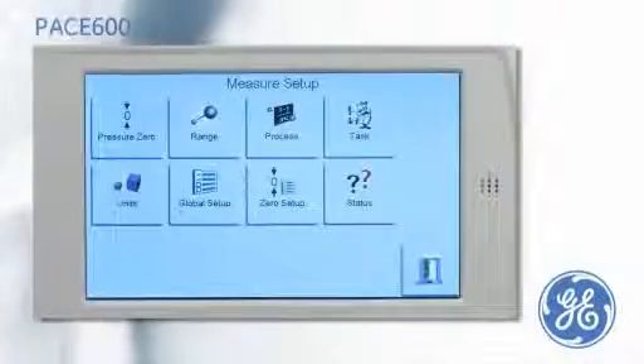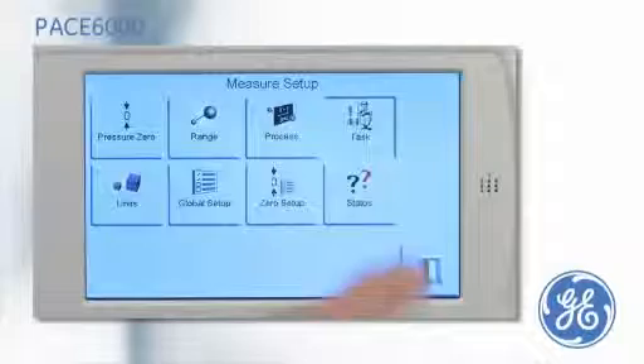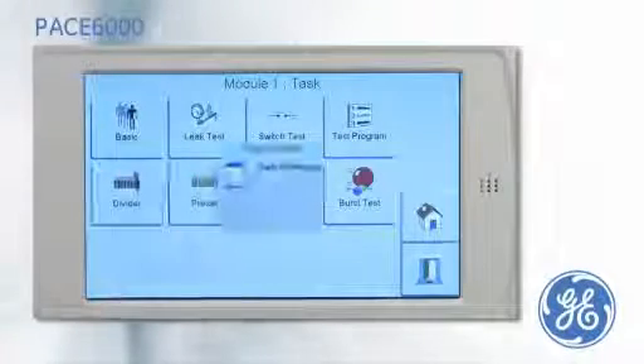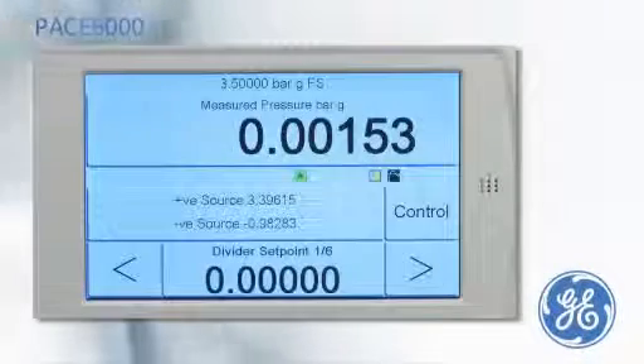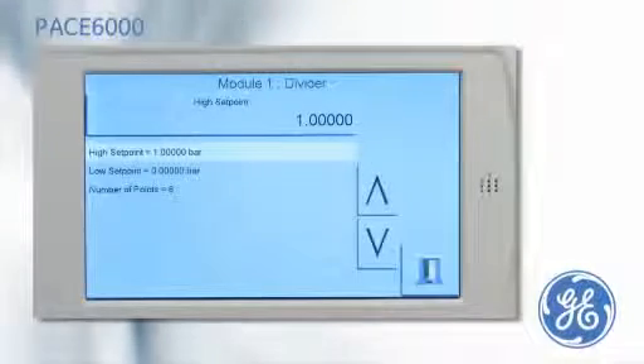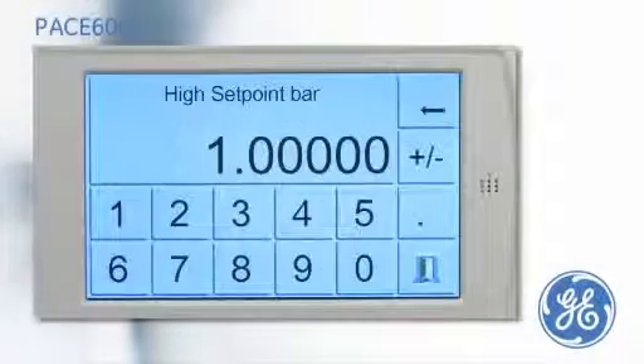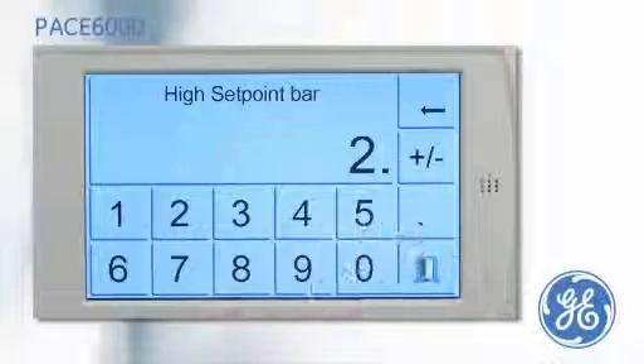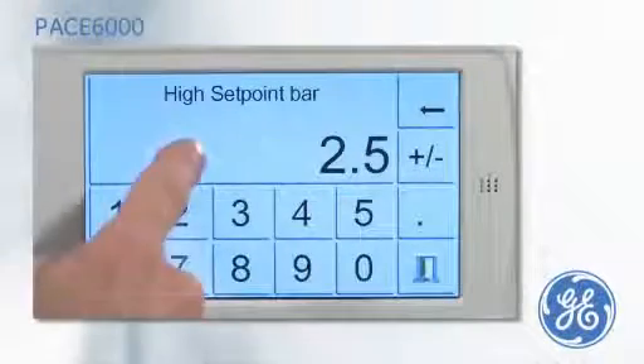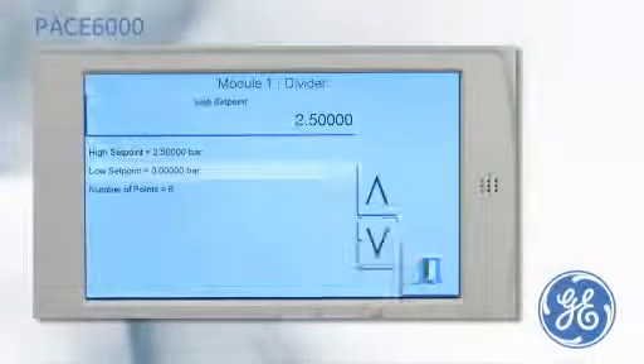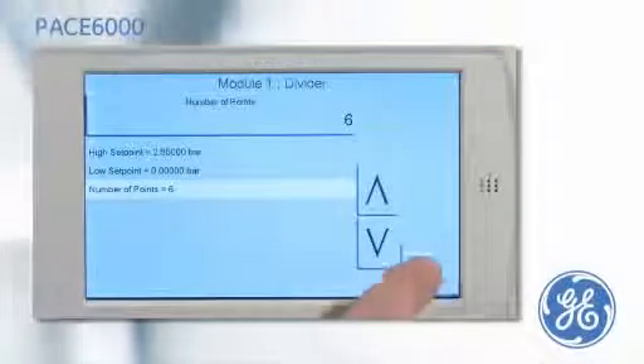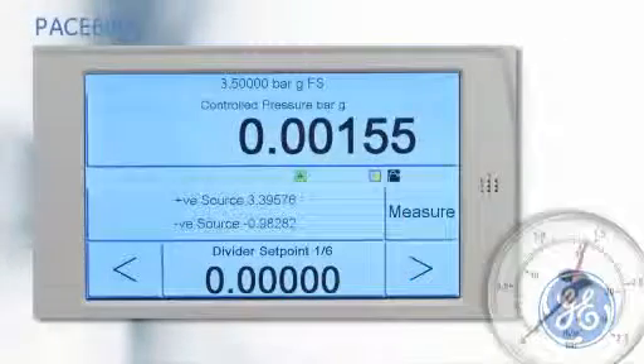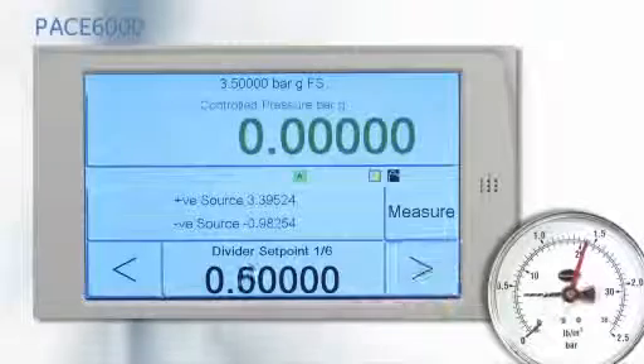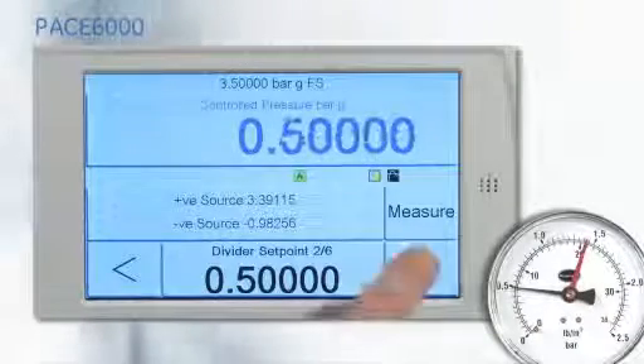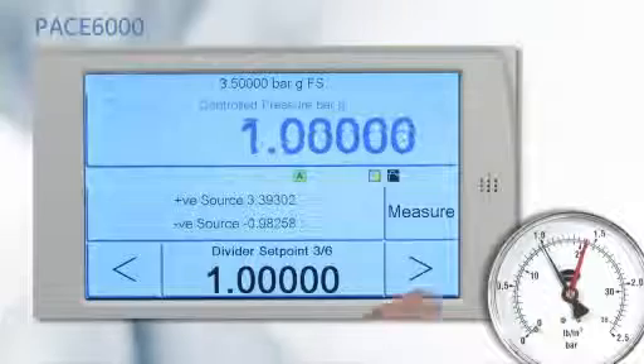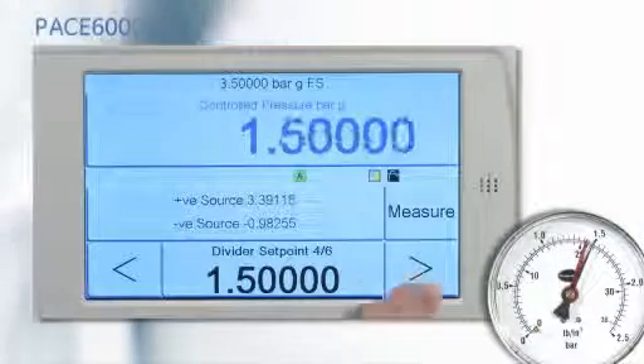An alternative to entering the set point at every cardinal point is to use the divide task. A full-scale range of 2.5 bar is entered. The start point is 0 and the number of cardinal points is 6. After the PACE has been put into control mode, the pressure can be stepped through the cardinal points by simply pressing the nudge buttons.